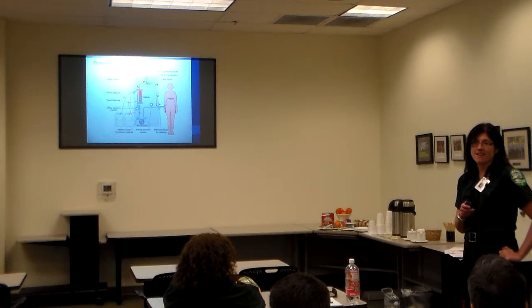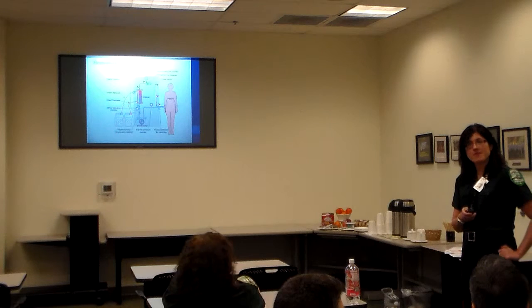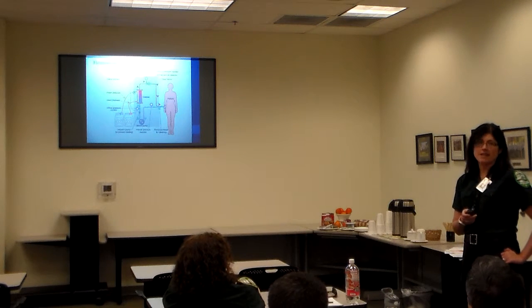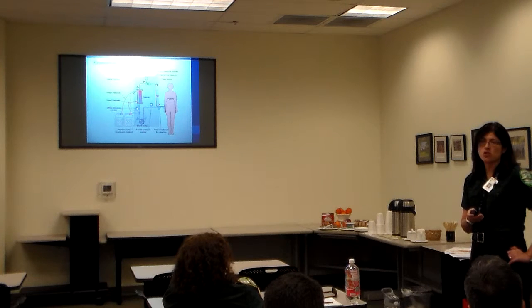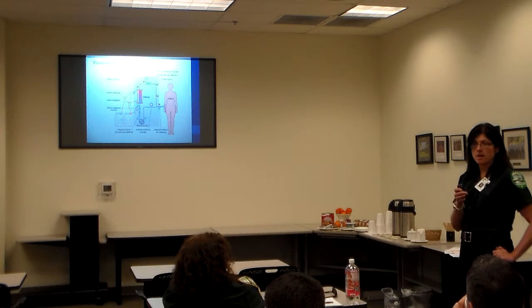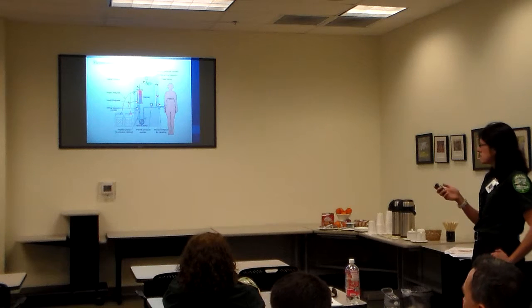Plus RO is wasteful. Yeah, like 6 to 1, I don't know what the liter or something is. It's crazy. That is a lot of water. That is how much a dialysis unit uses. And we do try to be thoughtful and put it down to what we call minimum flows in between patients. The machines will actually do that, but still, it's 500 mils a minute. It's a lot of flow.